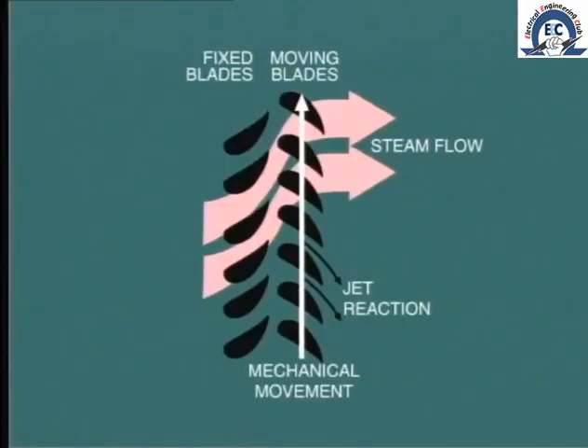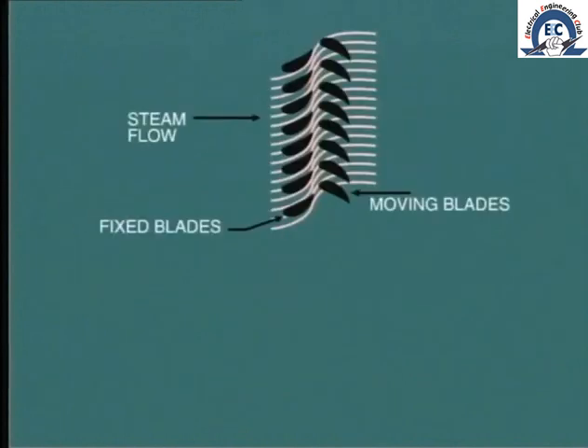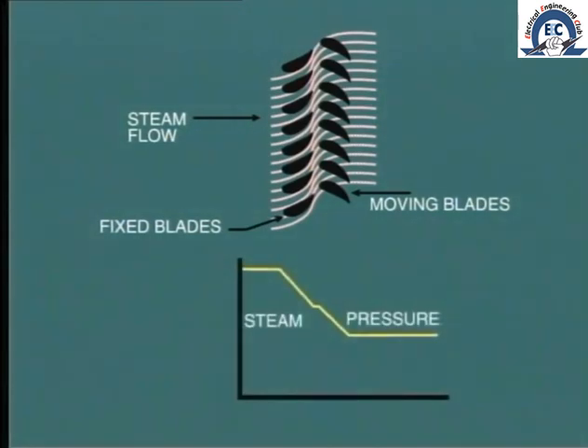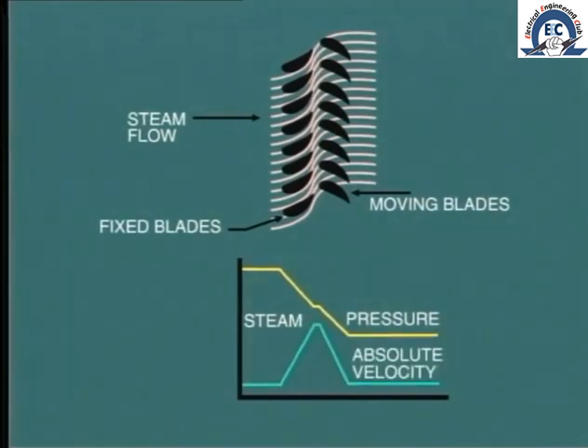Now let's move on to look at the characteristics of reaction type blading. In this case, the mechanical force on the blade is caused by reaction as the jet of steam exits from the blade. This is the same concept as a jet engine. With this type of blading, the moving blades are shaped in the same manner as the fixed blade, that is in the profile of a curved nozzle. This causes the steam pressure to fall as it passes through the moving blade, resulting in an expansion of the steam and an increase in its velocity relative to the blade, causing a powerful jet action.